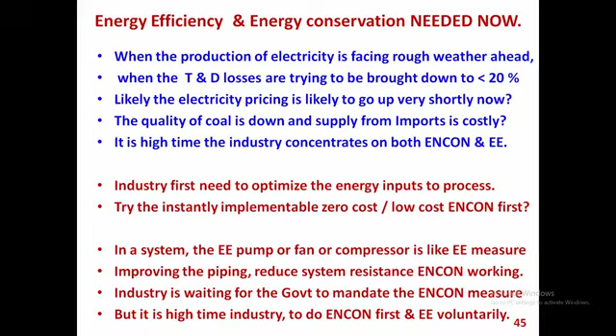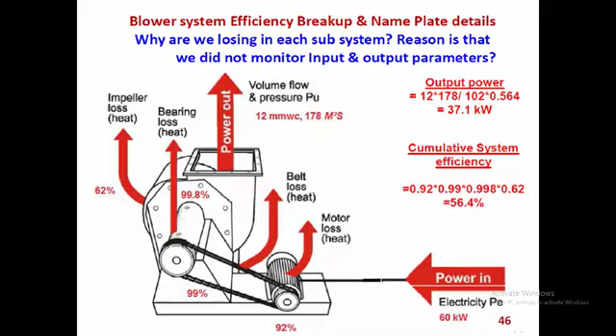I'm just going in depth on a blower, this one. A blower, normally a motor we say is around 80% efficient or 90% efficient. If you see, the blower's efficiency is around 56%, the system efficiency is only 56%. See, the scope for energy saving in blowers, pumps and compressors is very much more than in the motor. This is the main fulcrum where the energy auditors are working. We are working on the load side of any of the system, subsystem, utility and auxiliaries. Wherever we are able to put our hands, we are trying to manage, and we are able to measure the volume flow, we measure the Pascal with digital instruments, everything we have made digital measurements. Thanks to digitization and IoT monitoring, we are able to see a lot of inputs, the wrongness that is happening in the machines or in the process.